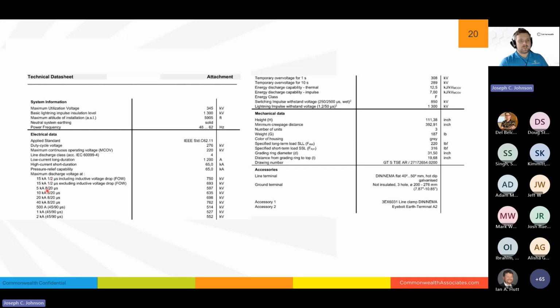As I mentioned before too, you can see these are all lightning events, these 8/20s. They go from 5 kA up to 40 kA. Well, what does this mean? Well, we see at a 5 kA lightning strike with that speed, we get these voltages, and these are what's called residual voltages. The arrestor is going to see this wave come in, and it's going to clamp the voltage, but it's not ideal. It's not going to maintain and only let 750 kV through every time, or 550 kV through every time. Depending on the wave steepness, its rate of rise, a bunch of very advanced things that determine wave speed, wave steepness, they will determine how much energy is actually let through the arrestor. And that's what these tests are meant to show.